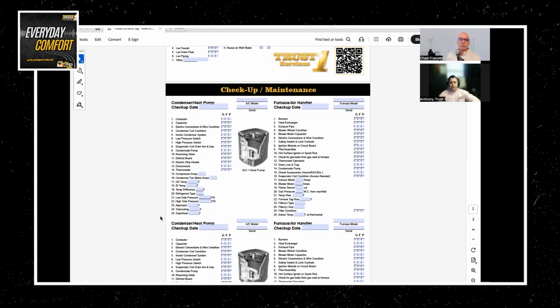So it skyrockets the pressure on the system, and that can actually cause components like capacitors and contactors to fail because it's pulling way too much power. So when we check the components for the power usage and the amps, it's high, and generally that's because either your compressor's failing or it has a fur coat on the outside of that condenser coil. So all these things are related. The pressure definitely is balanced by how the system's running. So those are all related components.